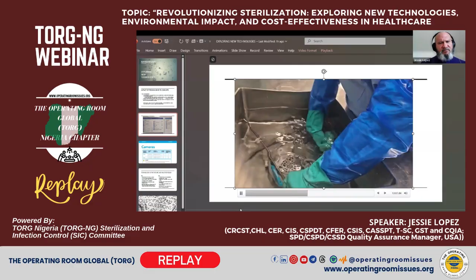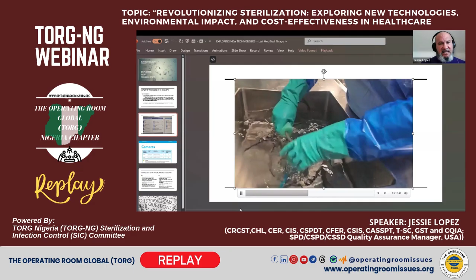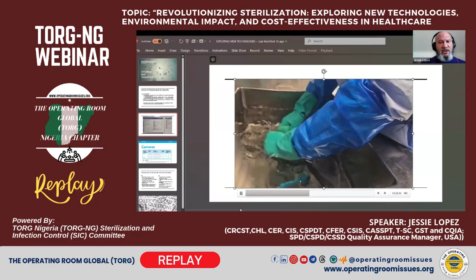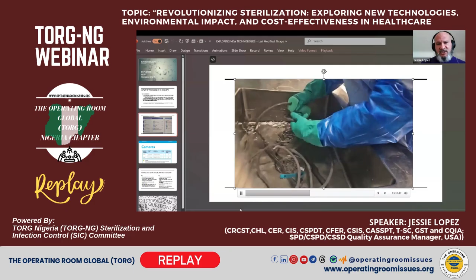Now, as you can see, you want to control that insertion tube to prevent that glass from hitting the side of the sink, because again, that can be easily damaged. Now, the cord can get tangled. You want to make sure that you're placing and grabbing it correctly and not putting too much force on it, in order to avoid damaging the cord. You're also doing your visual inspection as you're cleaning the device to see if you feel or see any residue left on the device.